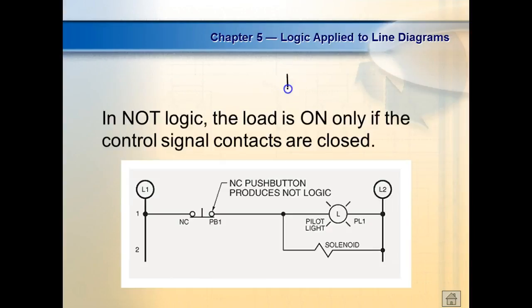Well, what's required here? Well, this is a NOT. So NOTs, NANDs, and NORs turn the load off. They're just opposite from each other. So notice what happened. This is a normally closed push button. So when I put power on L1 and L2, this light is going to be lit, and this solenoid is going to be energized. What happens when I push the button? The light goes out, okay, and the solenoid is no longer energized. So NORs, NOTs, and NANDs are what's required to turn the load off. And the ORs turn it on.